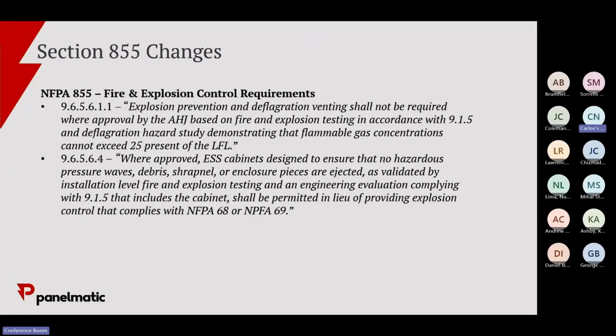Previous thought around this was, okay it's a fire, how do you starve a fire? Remove the oxygen. So if you just seal the enclosure, you can stop the fire from happening and try to stop the propagation that way. Well, when these are emitting hydrogen and VOCs in a confined sealed space, now you're essentially creating a pressure cooker with hydrogen, you're making a hydrogen bomb. Hence why this all of a sudden became a very big issue.